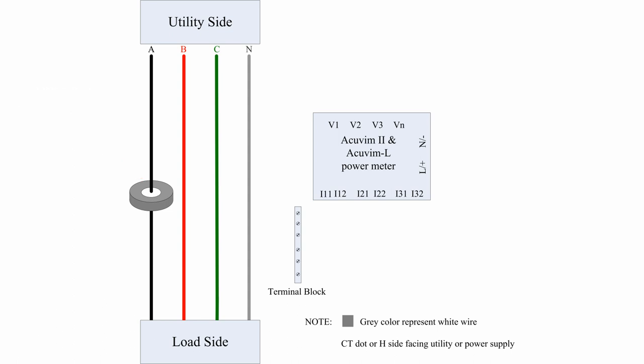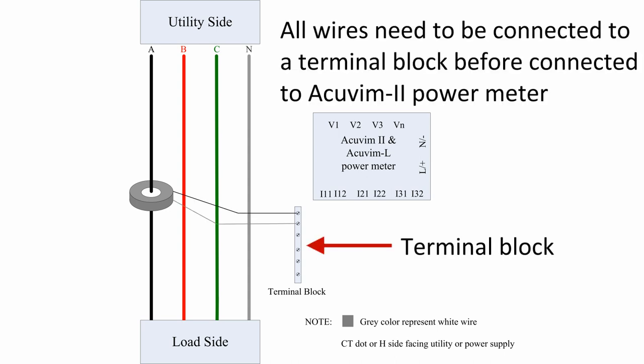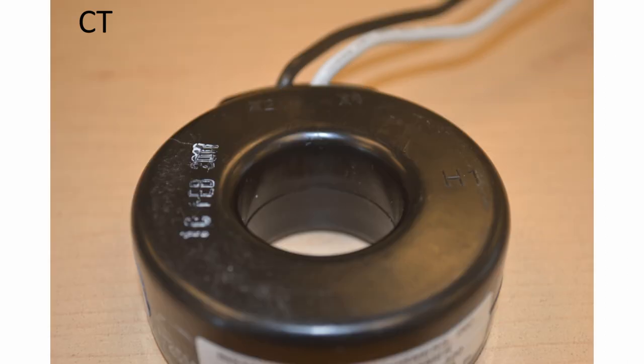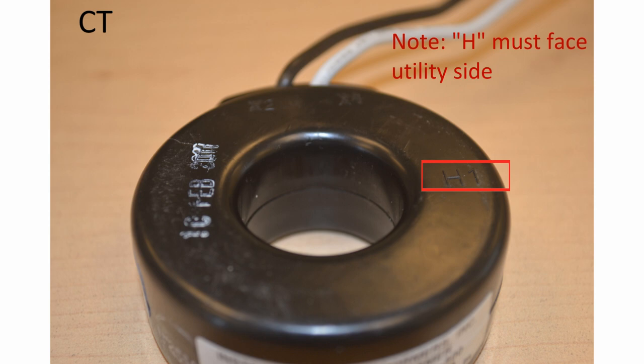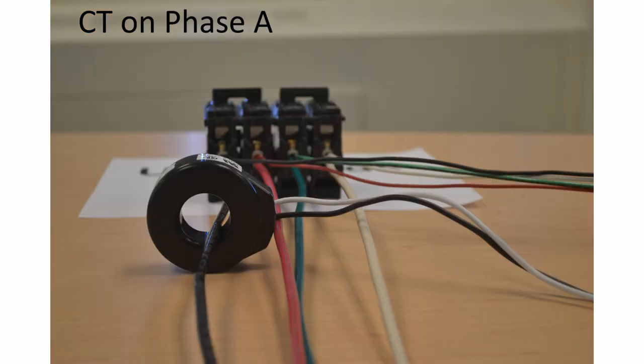All wires from the CT need to be connected to a terminal block before they are wired to the Acuvim II power meter. Please note this is a generic CT where the letter H must face the utility side to obtain accurate readings.